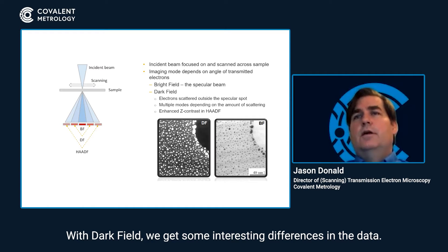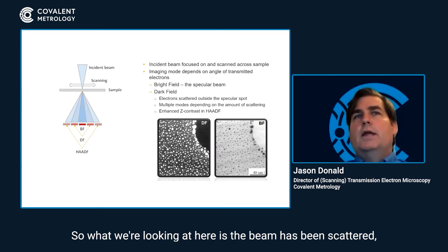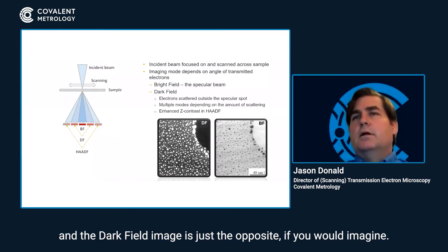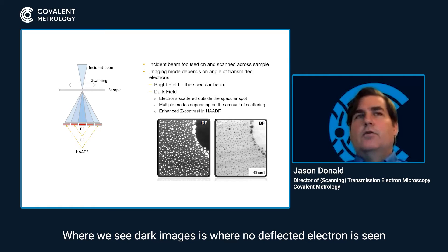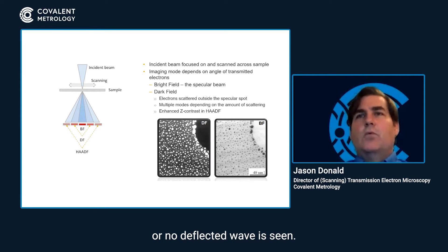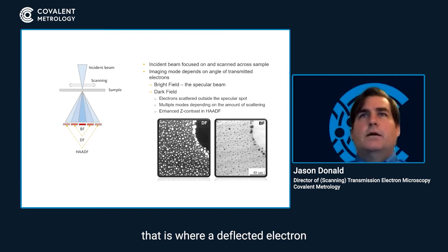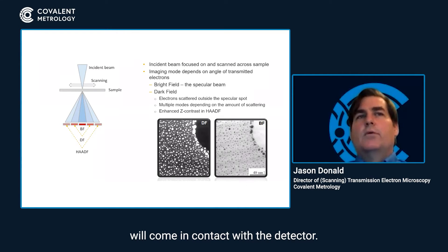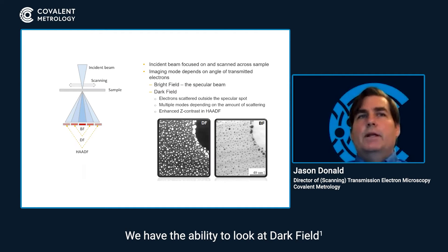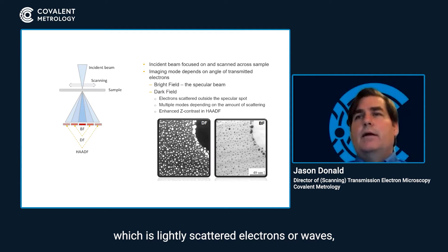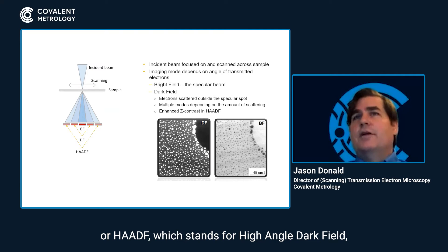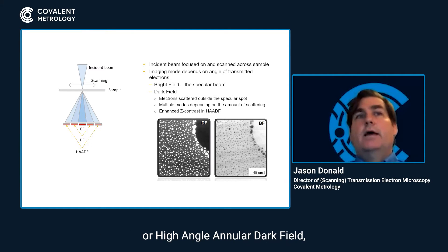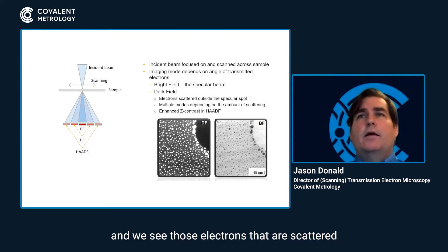With dark field, we get some interesting differences in the data. The beam has been scattered, and the dark field image is just the opposite, as you would imagine. Where we see dark images is where no deflected electron or wave is seen, and where we see bright images is where a deflected electron comes in contact with the detector. We have the ability to look at dark field one, which is lightly scattered electrons or waves, or HAADF, which stands for high angle annular dark field, where we see electrons scattered at a much higher angle.